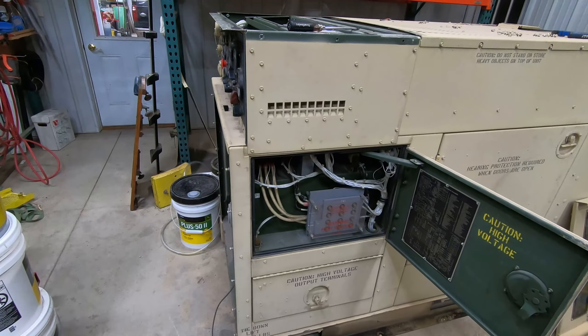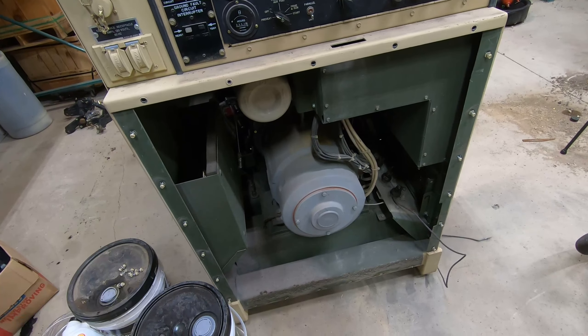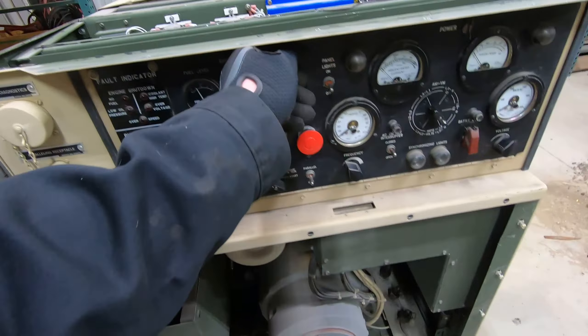I got it out the other day and it would not produce power. A couple things to note: it comes on, it'll run and start and everything. The convenience receptacle produces 120 volts, the hertz reads at 60, and the volts read at 208 or 120 depending on which leg. The only problem is when you close the AC circuit interrupter, nothing happens — there's a brief flash but nothing else. I'd already pulled the front cover to check if a rat or mice had gotten in and chewed wires, but I didn't see anything like that.